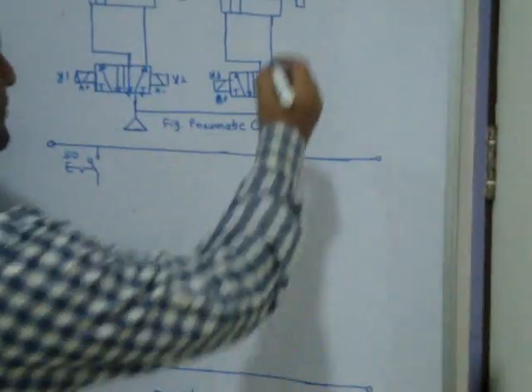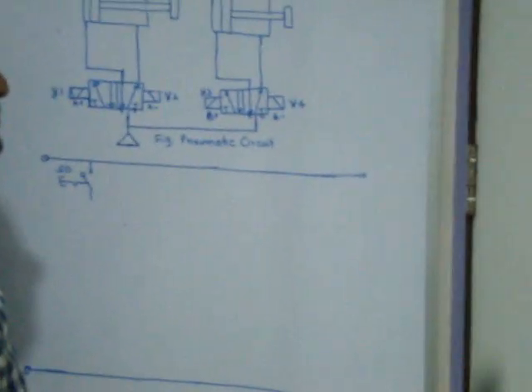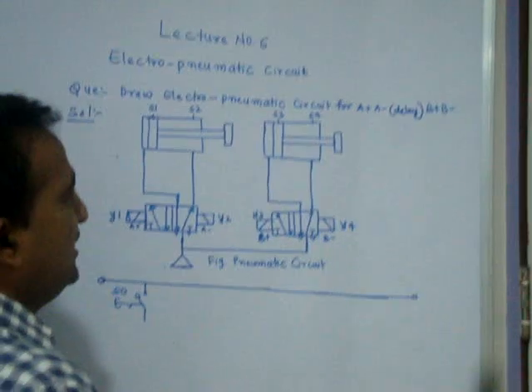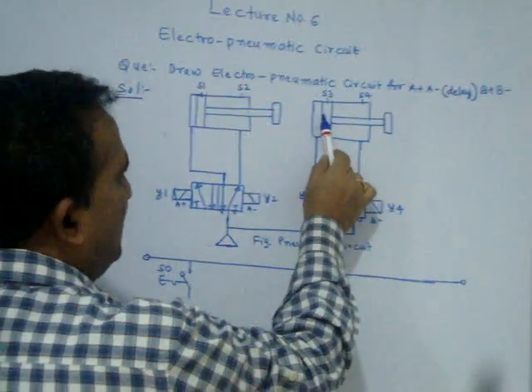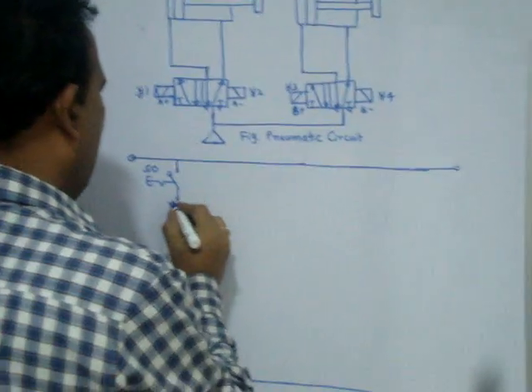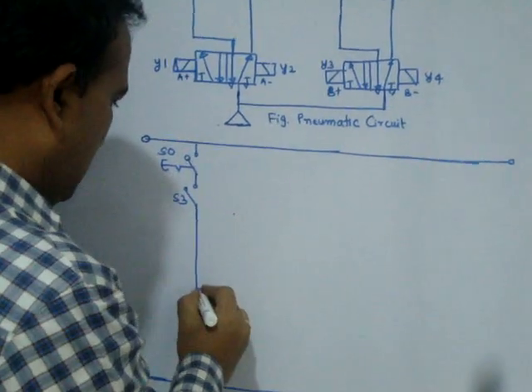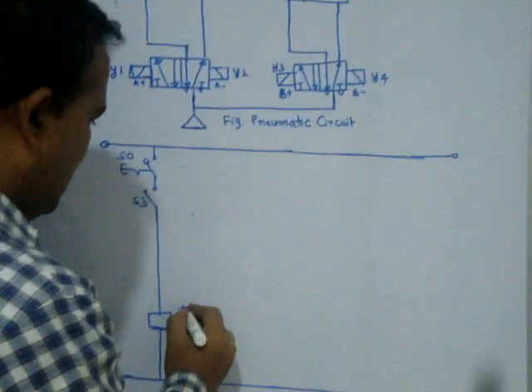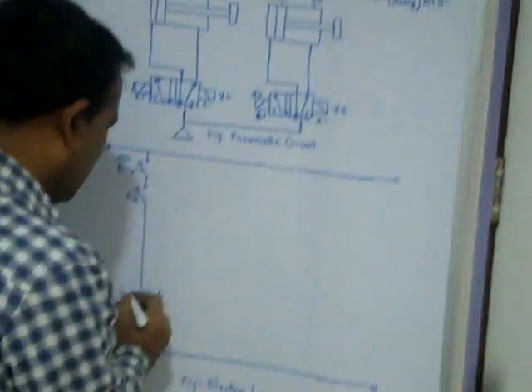Now I'll start. The first sequential action is A plus. For A plus, some reference is required. A plus is nothing but Y1 — you can take directly A plus or Y1. If I take Y1, the reference I take is S3. The last action is B minus, meaning the piston comes to S3. So I'll take S3 as the reference. When S3 is on, Y1 should be on. This is the symbol for the solenoid, and the name of this solenoid is called Y1 or A plus.